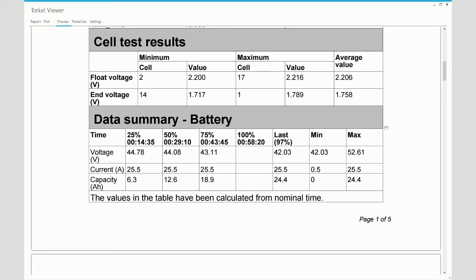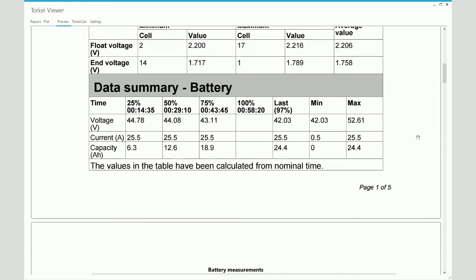Below that, you see a summary of the overall battery test data. So you see the 25%, 50%, 75% values, and you don't see the 100% values. And that's because the test didn't reach the 100% level. It stopped before the intended duration of one hour.